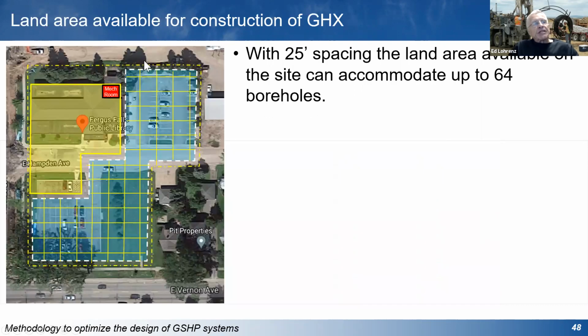Next, we have to look at how much land area we have to play with. Based on 25-foot spacing, we could accommodate up to 64 boreholes on this site. So we know how much land area we've got. Once we know how much total borehole length we need and what the thermal properties of the soil are, we can design and model the ground heat exchanger.